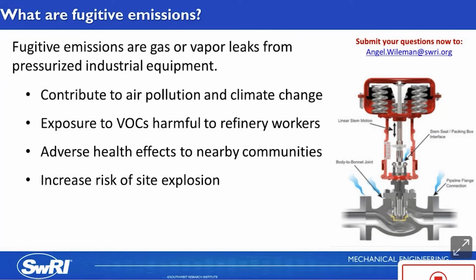So here is an image of a valve, and it shows the typical fugitive emission areas. You have the body seals, such as the flange joint between the valve body and bonnet. Also the end flanges on the valve that connect to the process pipeline. These areas must be checked for emissions, but they are static seals, so they typically have lower leakage than a stem seal. The stem seal is the primary leak path because it is a dynamic seal. The stem will move up and down during operation, transmitting linear motion from the actuating device to the wedge or the disc that's permitting or preventing flow.